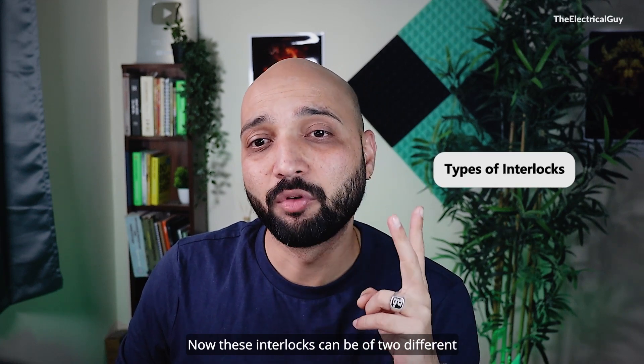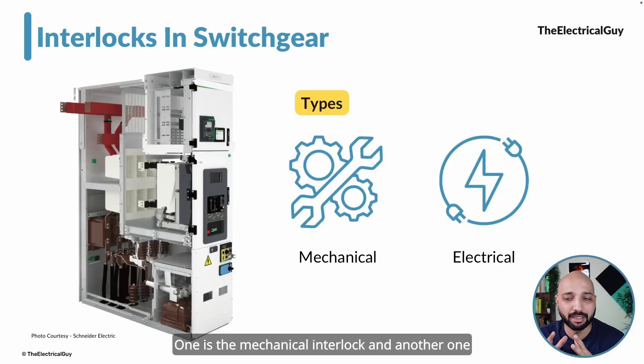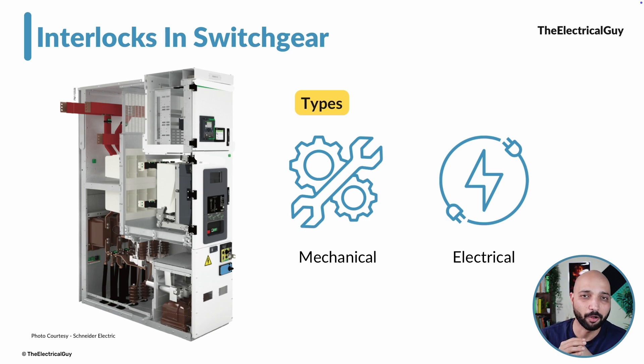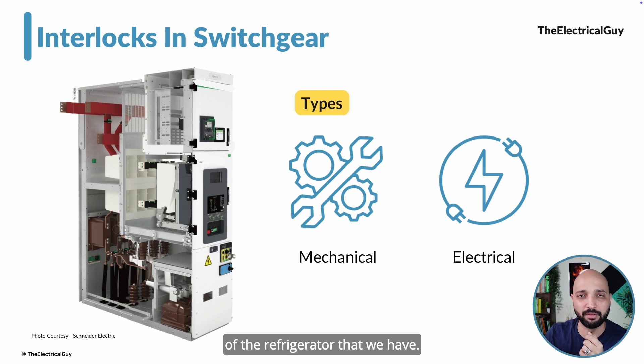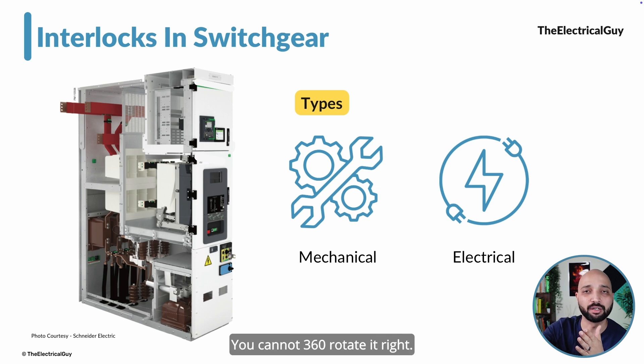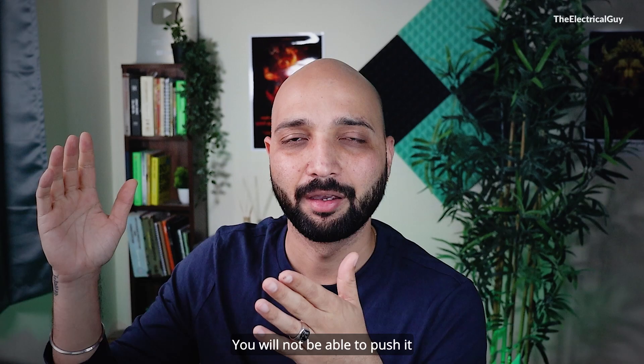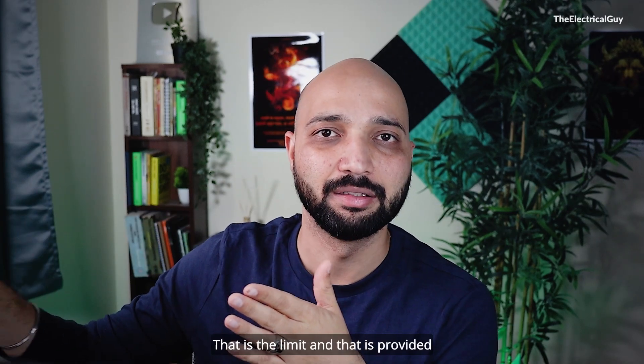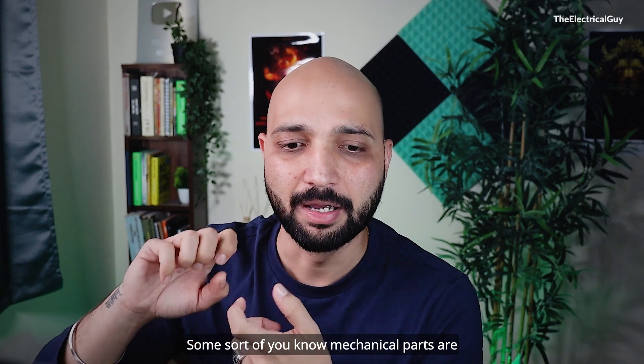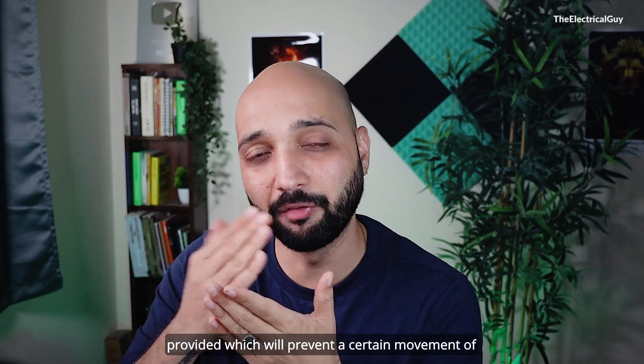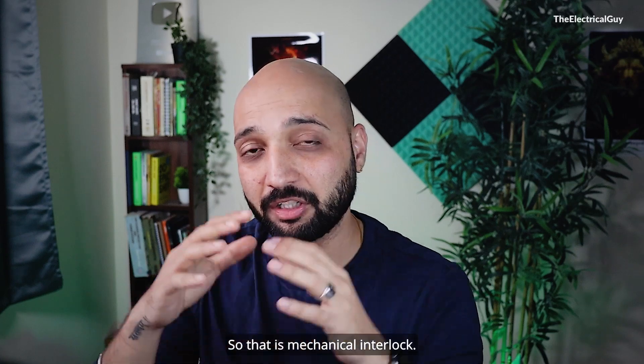These interlocks can be of two different types: mechanical interlocks and electrical interlocks. Mechanical interlocks are pretty common, not only in switchgear but everywhere. Take the example of a refrigerator door — you can only open it to a certain degree, you cannot rotate it 360 degrees. You open it to the limit and it gets stuck. That limit is provided by a mechanical interlock — some mechanical parts are provided which prevent a certain movement.